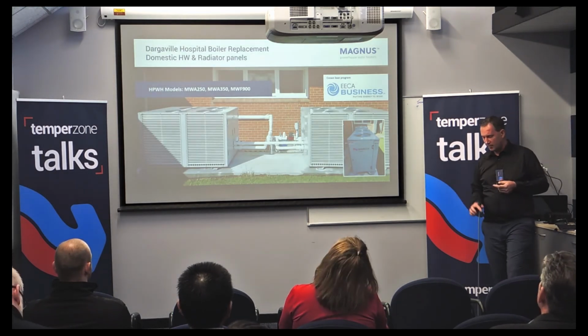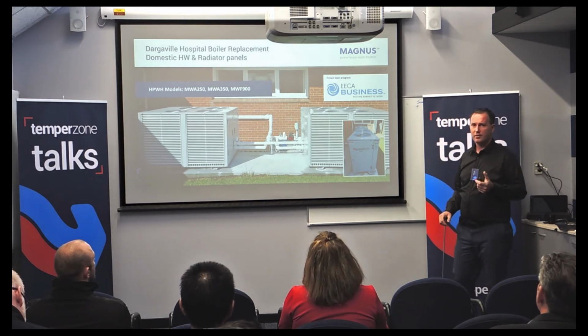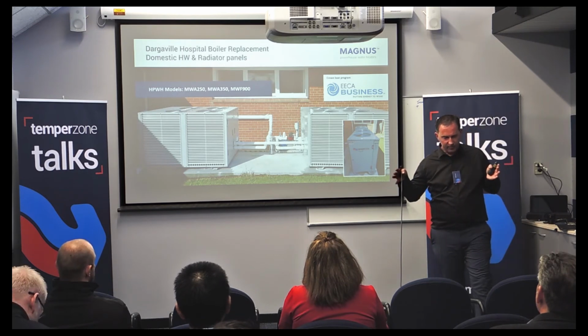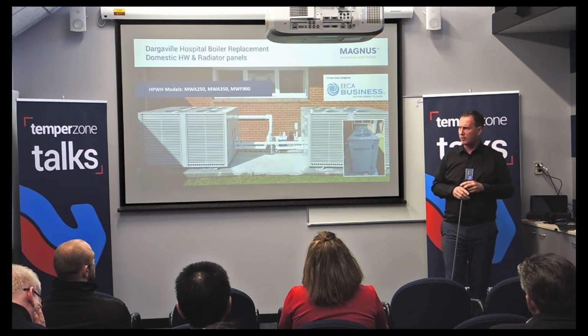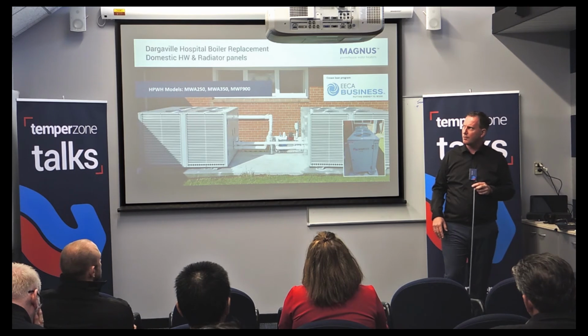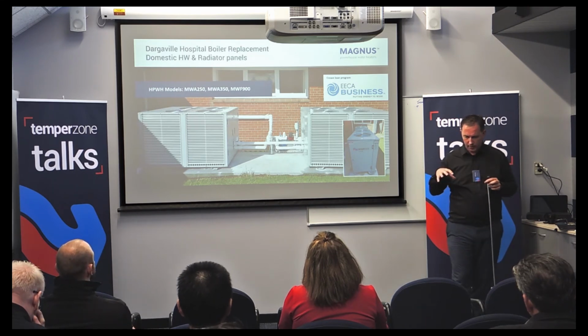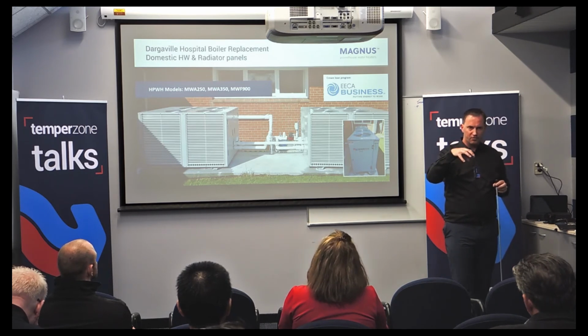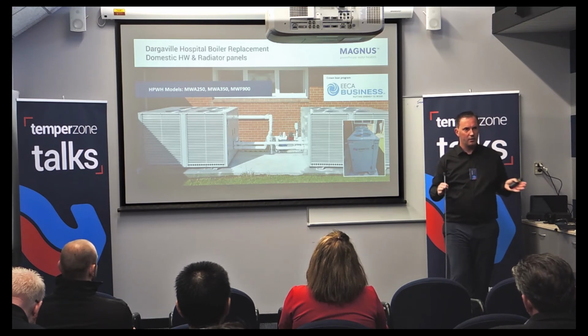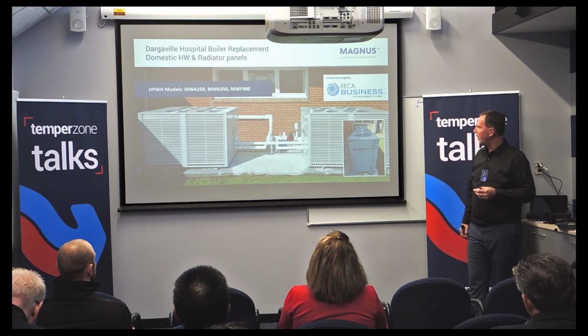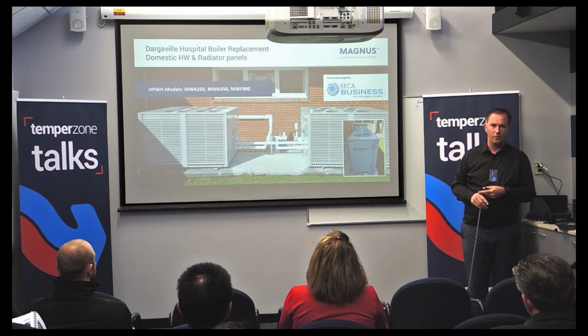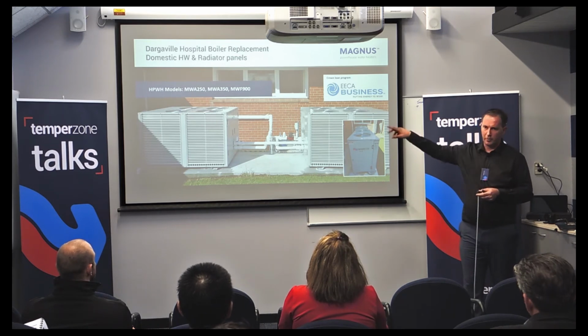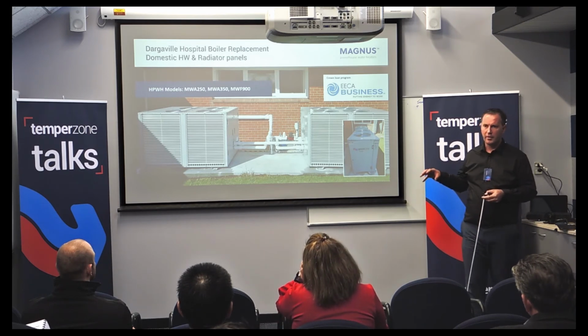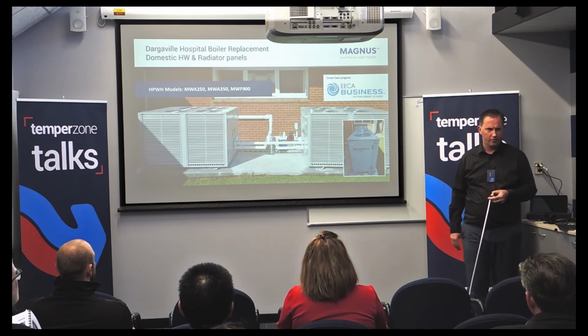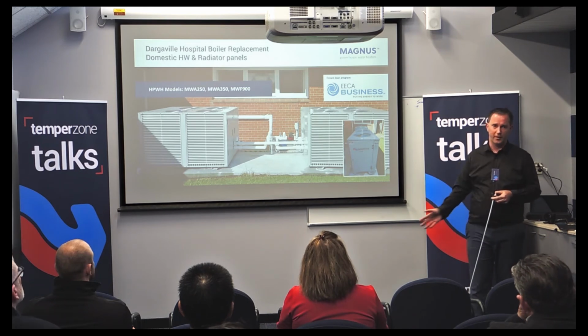Another project is a water heating replacement project. So this project took a central diesel boiler that had a primary circuit that went around 4 buildings of a hospital, and we removed the diesel boiler and we did a distributed heat system. So we split off the space heating from the potable water heating. The space heating only operates around 8 months a year, and the potable hot water obviously goes the whole year round. And there's big tunnels under the buildings where the plant is, and by removing that primary loop, the tunnels went from, in the middle of July, very, very warm, after the heat loss coming off, to very stark.